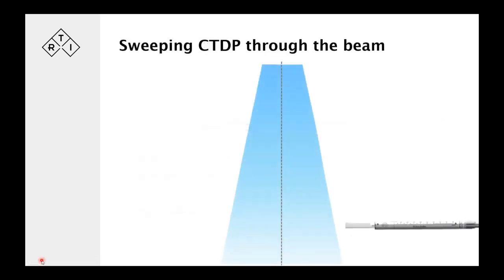And the method then would be something like this if we illustrate it. We've got a beam, the CT dose profiler. There, it looks like a pencil ion chamber, but remember there's a point dose detector planted smack in the middle of this detector right there. So there's one sensor that we have in place. The thing we need to work on is we need to know the speed of travel.